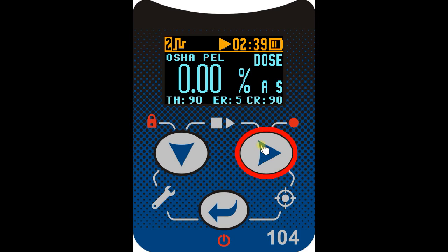Let's just go to the third dosimeter by pressing the right button again here, and we'll see that for dosimeter 3 the setup name is the ACGIH settings. Here we have a threshold of 80, an exchange rate of 3 dB this time, and a criterion for our 100% noise dose of 85 dB. So one more press of the right arrow key will bring us back to our primary dosimeter in profile number 1 here. So this is how we get around the 3 dosimeters. This button just simply takes us between dosimeter 1, dosimeter 2, dosimeter 3 and back to dosimeter 1.